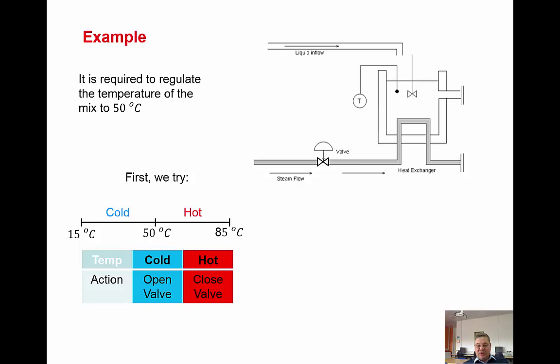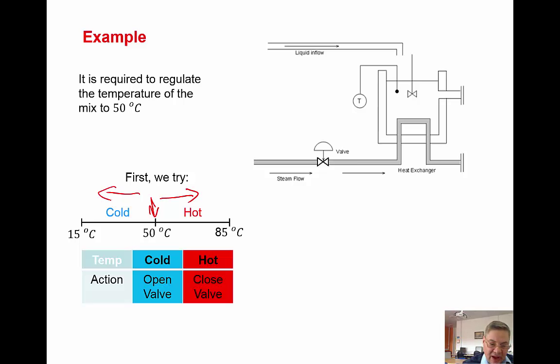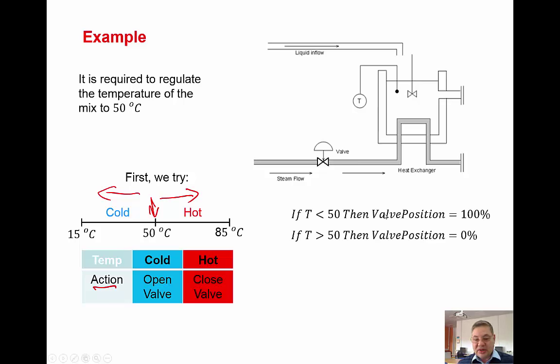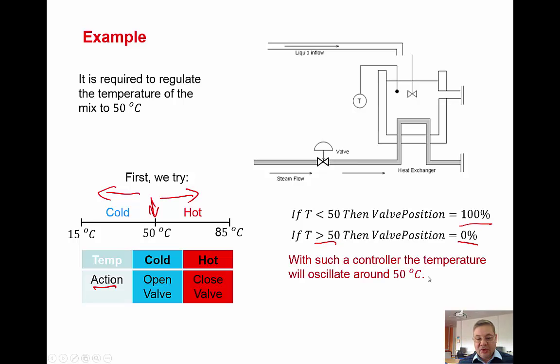The first approach: if 50 is my desired temperature, then if it's above 50 I say it's hot; if it's below 50 I say it's cold. If it's cold, the action is to open the valve; if it's hot, the action is to close the valve. This is like a relay controller — an open/close action. Implementing it is just two simple if-then statements: if temperature is less than 50 then valve position is open; if temperature is greater than 50 then valve position is closed, or zero percent.